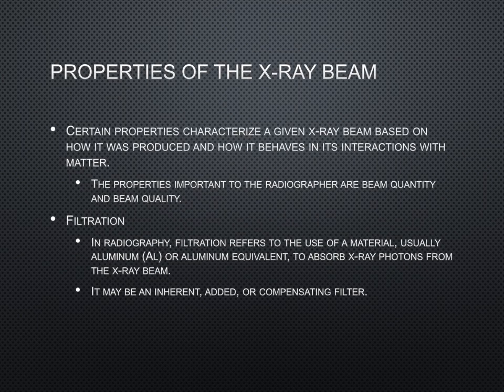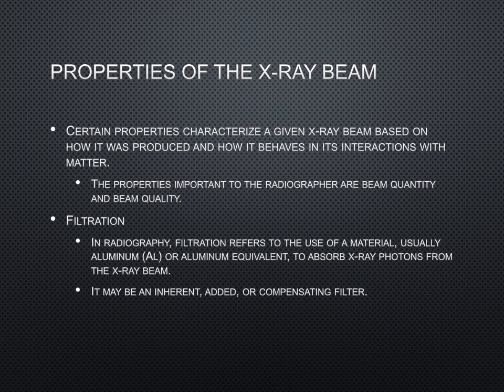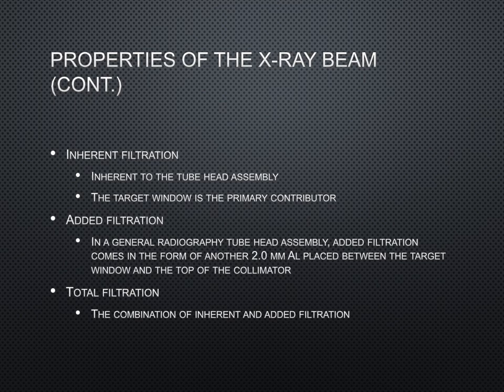Certain properties characterize any given x-ray beam based on how it was produced and how it behaves in its interactions with matter. The interactions with matter are covered in detail in my video about Chapter 7, Interactions with Matter. The properties that radiographers should be familiar with are beam quantity and beam quality and the defining terms of each. Before we get to that, a discussion of filtration is in order. In radiography, filtration refers to the use of a material — usually aluminum or an aluminum equivalent — to absorb x-ray photons from the x-ray beam. This filtration may be in the form of an inherent, an added, or a compensating filter.